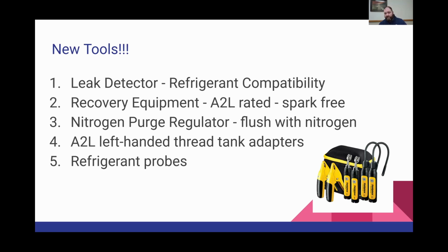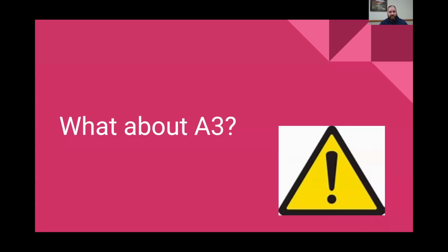And then the other thing I love about where our industry is going is the technology with refrigerant probes. So now I can put my two refrigerant probes as shown in the bottom corner here, and you can pick whatever brand you want, doesn't matter. They just had a nice picture of this Fieldpiece set. So the two probes in the middle, I screw those on, and I'm taking no refrigerant from the system or hardly any refrigerant from the system. And I connect to it via Bluetooth and I tell it what the refrigerant is, and it just communicates so I don't have to look at gauges and convert pressures to temperatures and charts. To me, it makes it much more simple to service, and you can document stuff a whole lot better, which as a contractor to me is the real benefit.